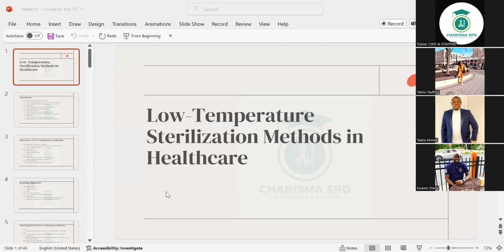So this is what we're doing today. What I expect us to get from this is to discuss basic requirements important for low temperature sterilization systems and to explain specific requirements for low temperature sterilization. We have at least three methods that we'll be looking at: ethylene oxide, hydrogen peroxide, and then ozone. If you are asked for three examples of methods of low temperature sterilization, it's ethylene oxide, hydrogen peroxide, and ozone, okay? So we will review important parameters of the low temperature sterilization methods. And I've told you the methods are these three: ethylene oxide, hydrogen peroxide, and ozone.